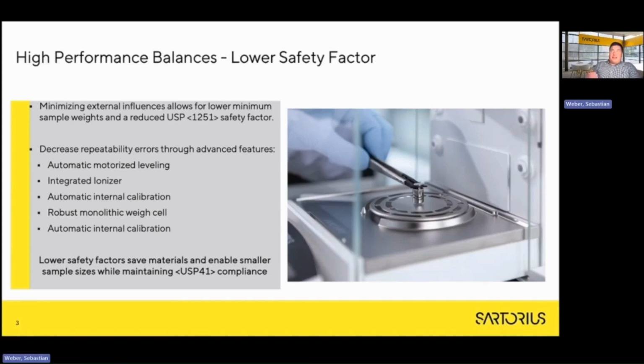Features that help you achieve this are motorized leveling, an integrated ionizer to remove static, internal automatic calibration, and also a robust weighing cell that reduces drift in the end. And why does it matter to reduce the safety factor? Because it enables you to weigh smaller sample weights. This saves material and time in the end, especially when you have very expensive active ingredients. What we know from the pharmaceutical industry is that it also saves money in the end.